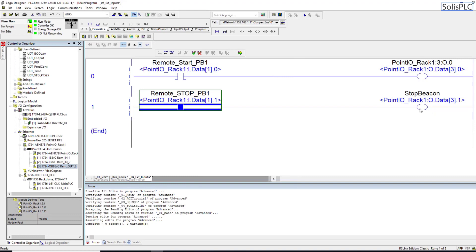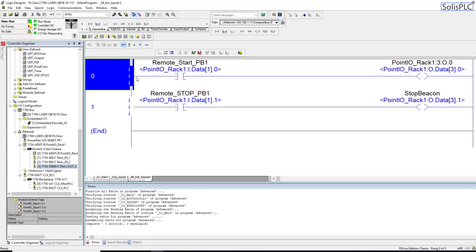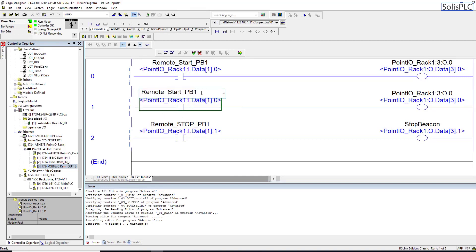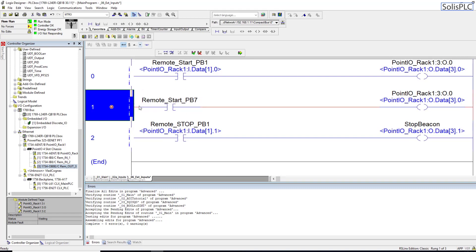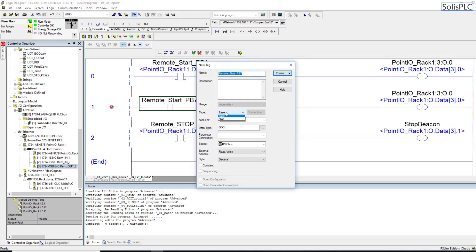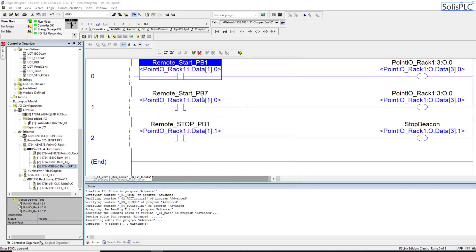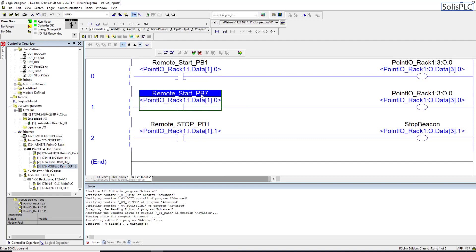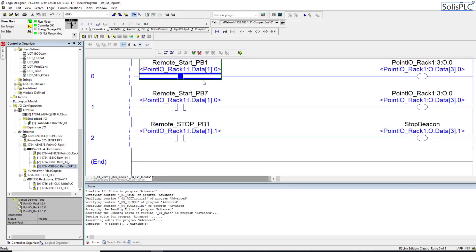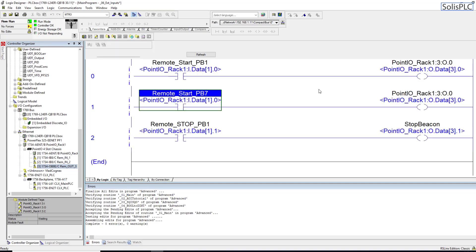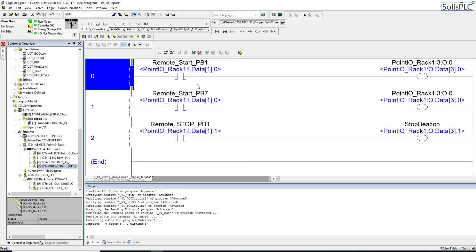That pretty much sums it up for the alias. One thing I do recommend you watch out for is once you start copying and pasting a lot of these, it becomes difficult to troubleshoot. For example, push button seven can also alias the exact same tag. This is going to be confusing when you cross reference because in your mind you're seeing that they're different and the tag names are essentially different, but when you cross reference they're always referring to the same exact tag. The reference is different but the base tag which is your alias tag is going to be exactly the same.